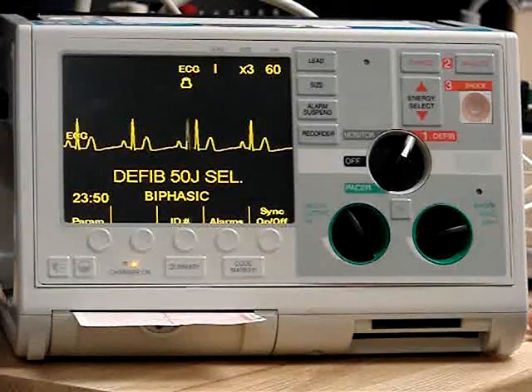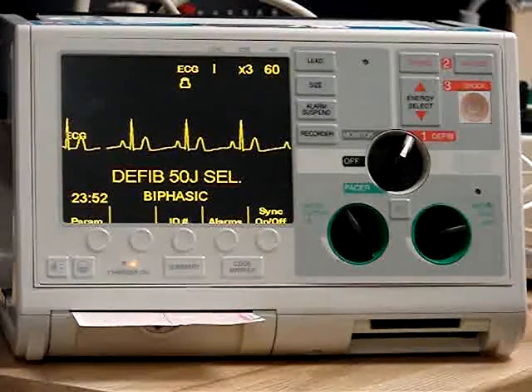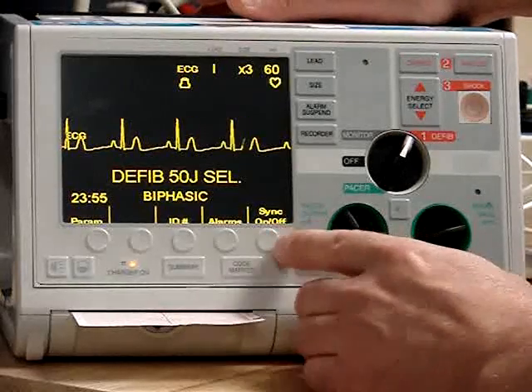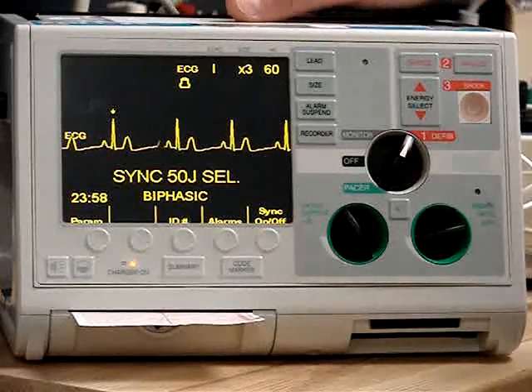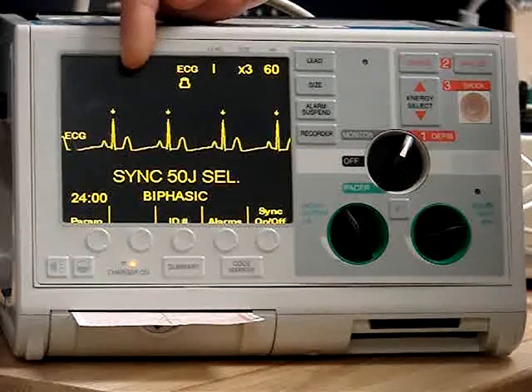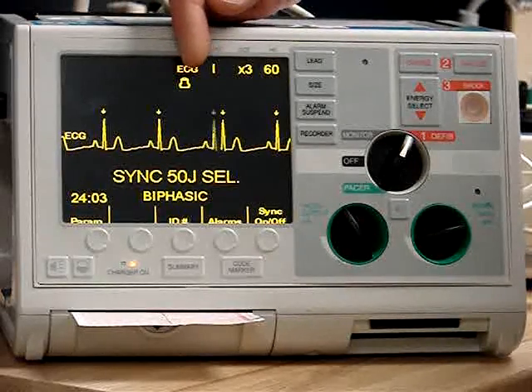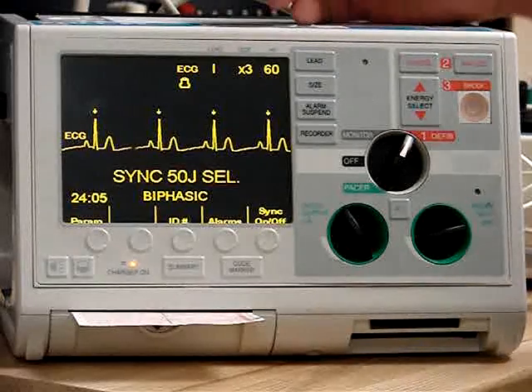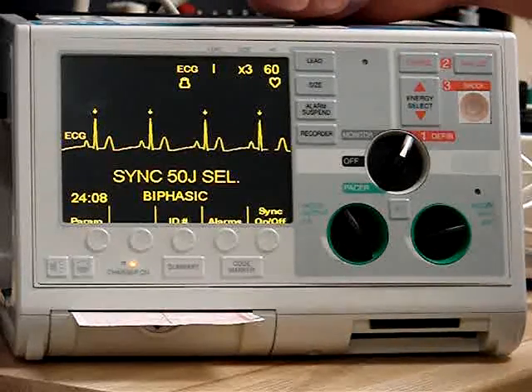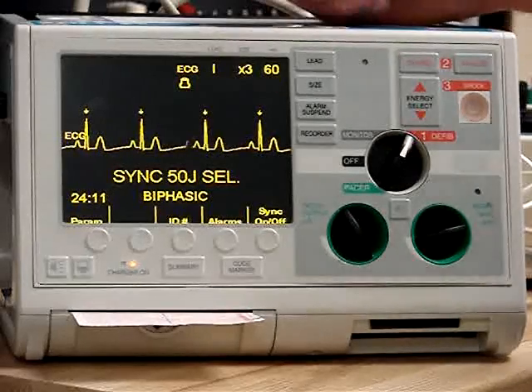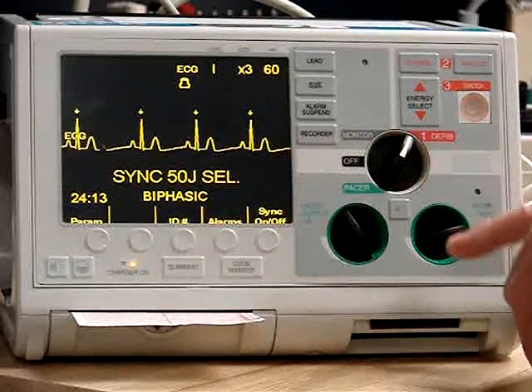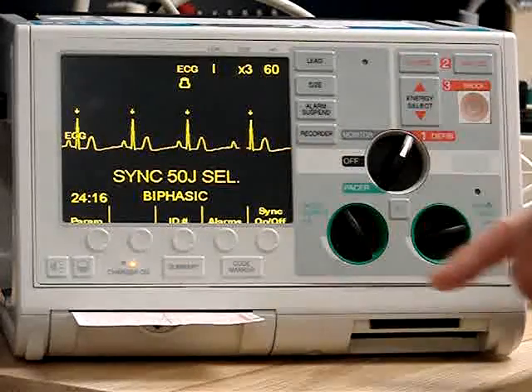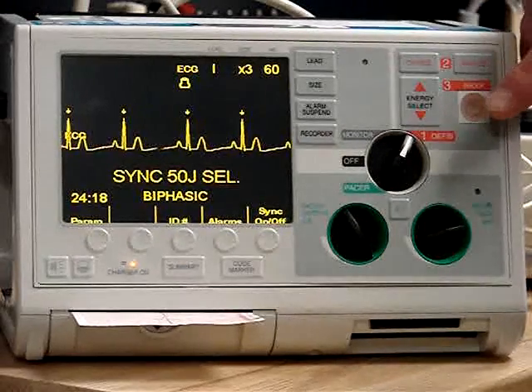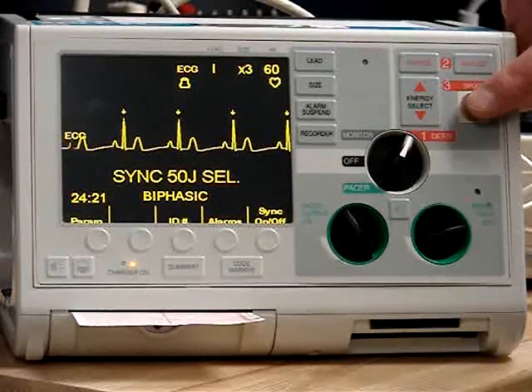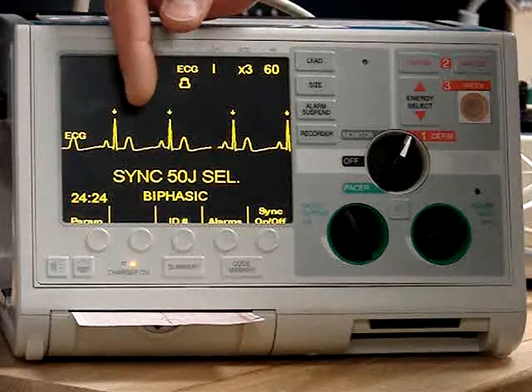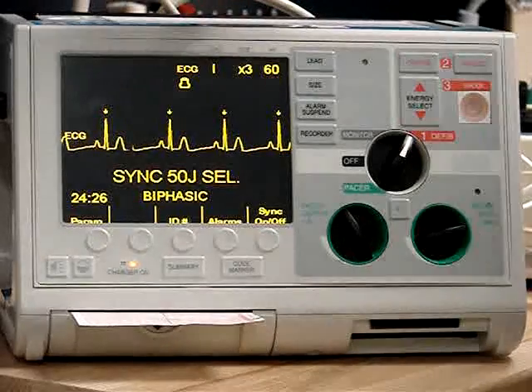So now we're going to check the synchronizer recorder function of the defibrillator. First, by selecting synchronizer on, we now see that the defibrillator is marking each R wave. This function is to check that it only discharges in sequence with the R wave. So we want to select 50 joules with our energy select, and we already selected that. We're going to charge it, and then when we get a shock advise, we're going to push the shock, and it will not shock until it comes in contact or at the same time with the R wave.